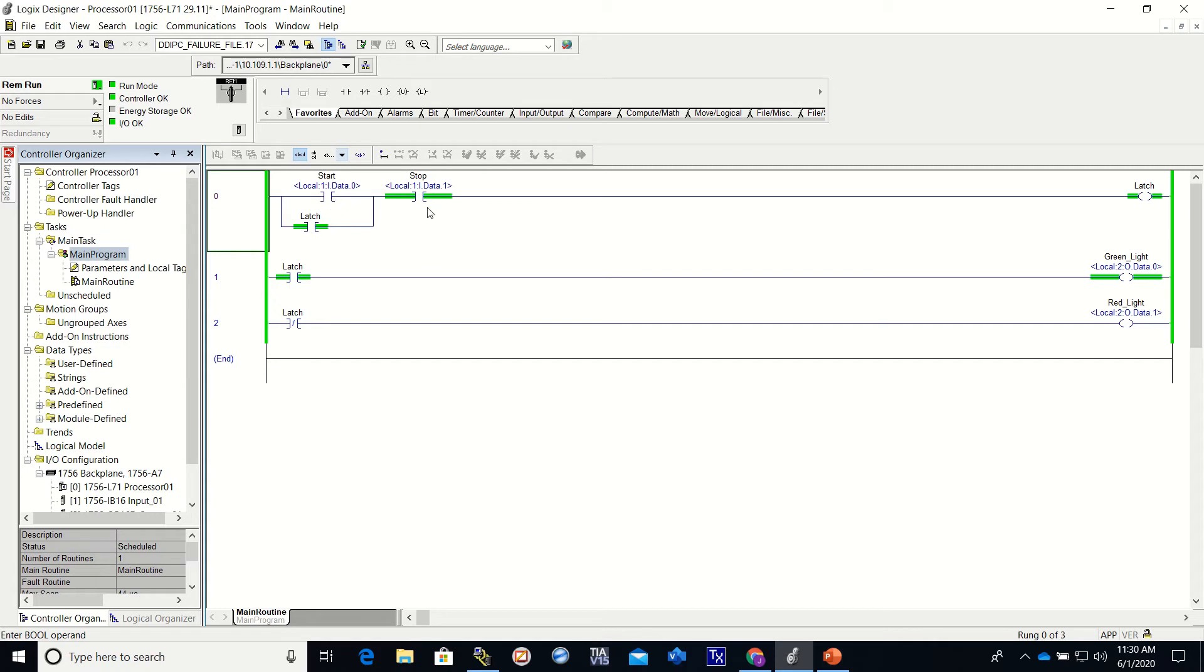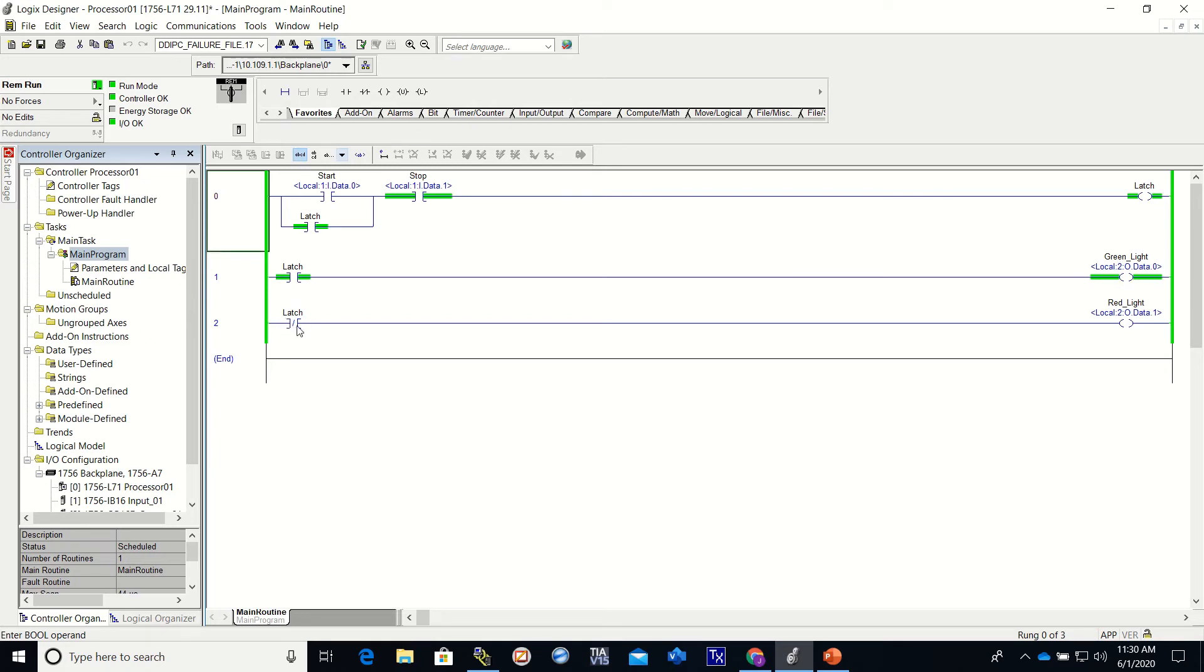I'm going to release the start button. You can see that this went away. We are being held on through the latch, through the input of the normally closed stop button, holding the latch on. And the latch is holding on the green light. The examine off went off because latch came on, therefore the red light went off.